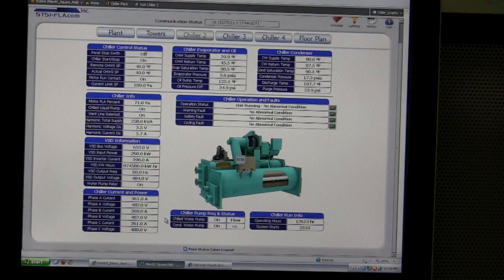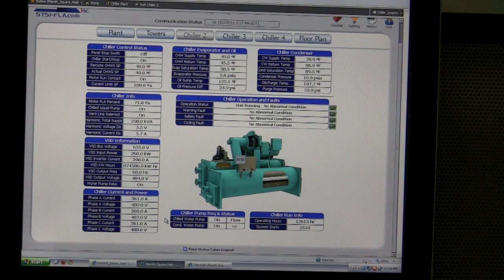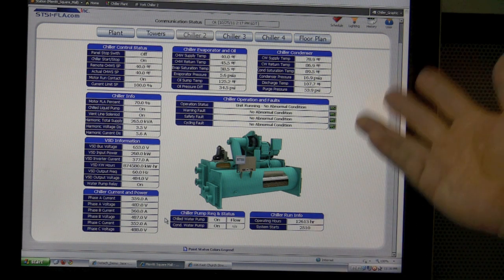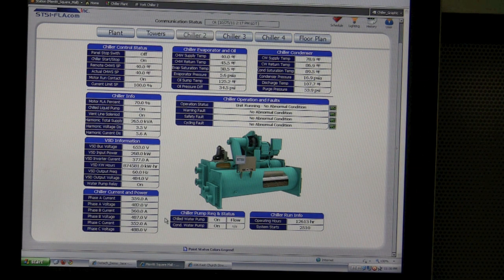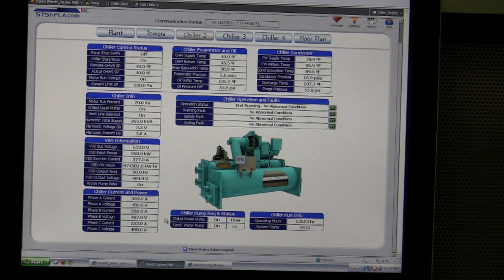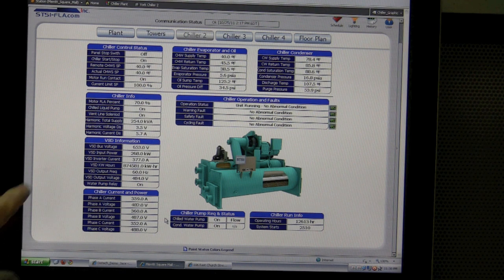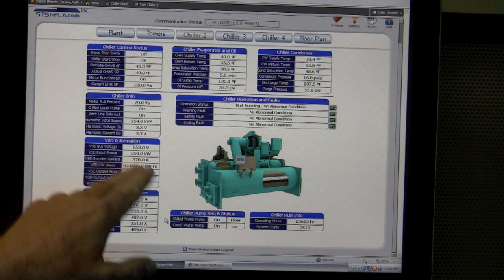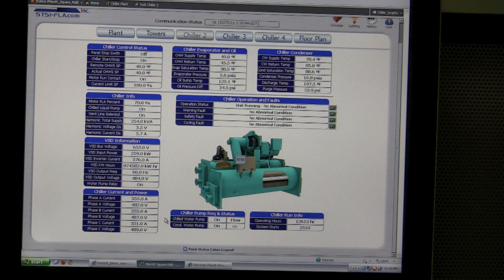We're start-stopping the chiller — this is a York chiller with an N2 interface. We've got all the data right here on the graphic that you would have at the front panel of the chiller. This is live data from the mall right now — this is what the chiller is doing. You can see the voltage coming in and the KW input that they're using.